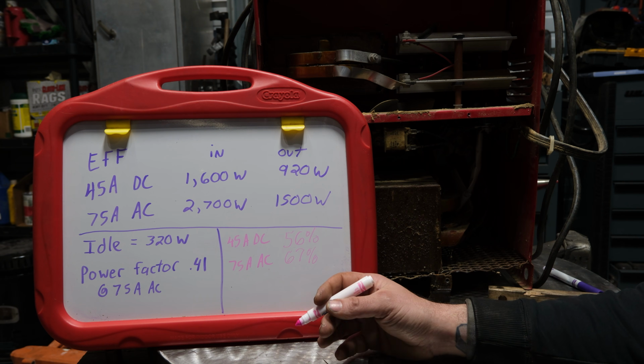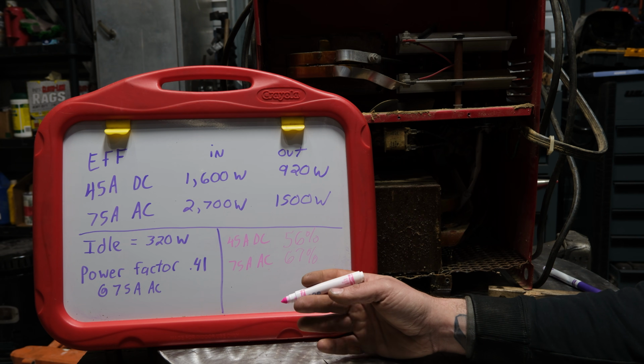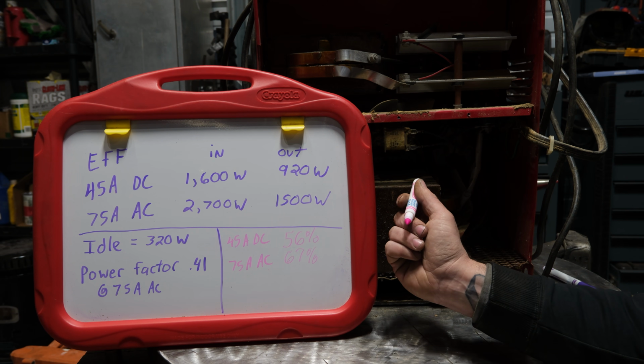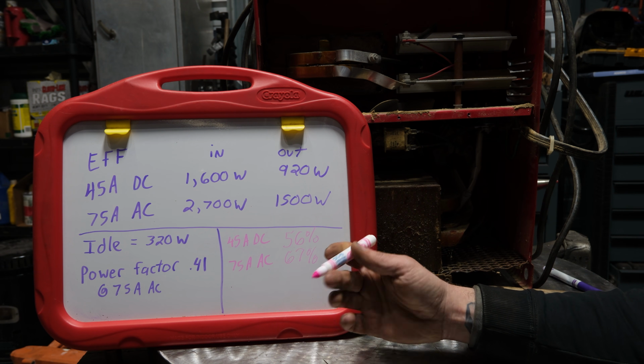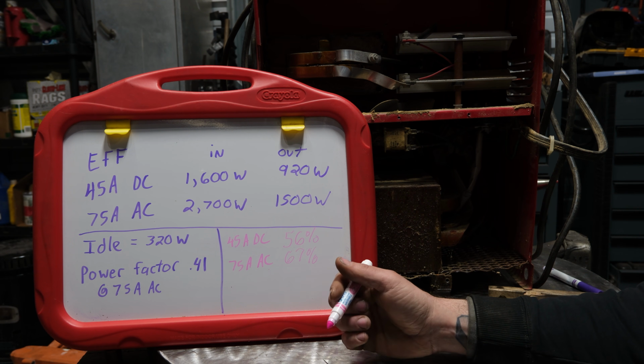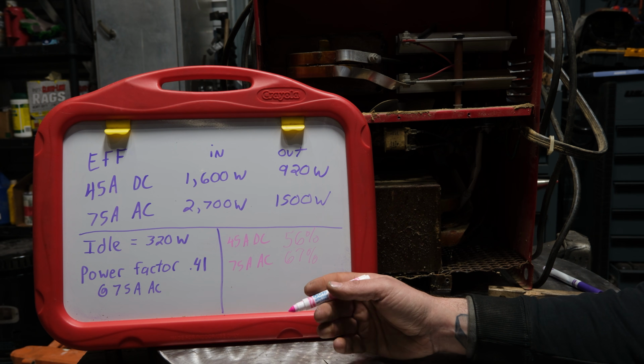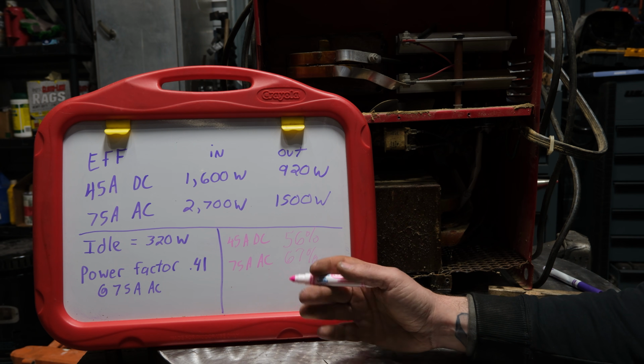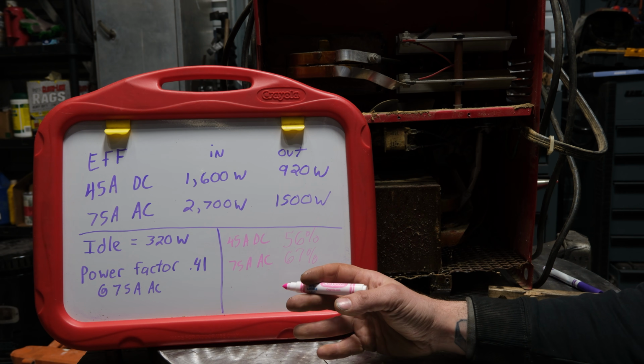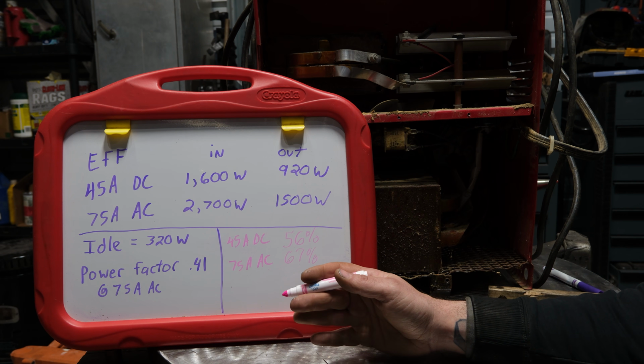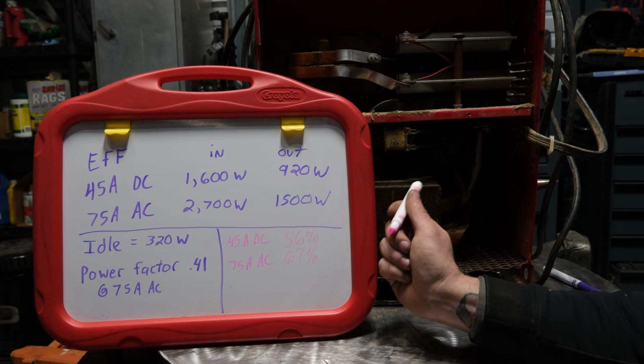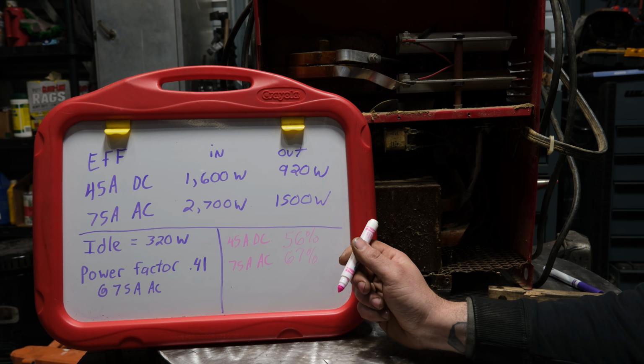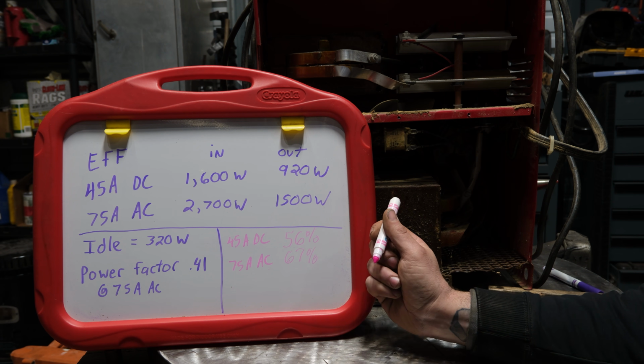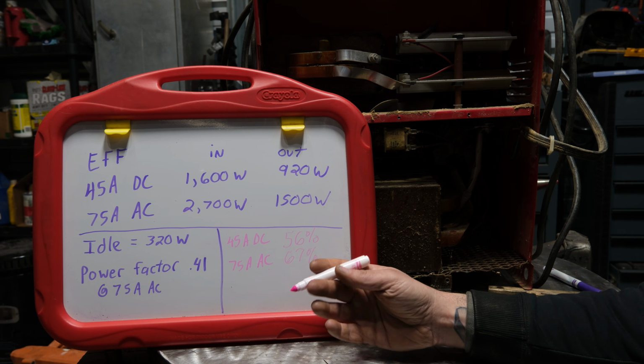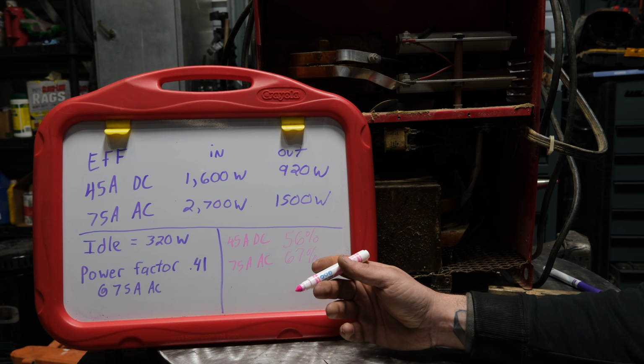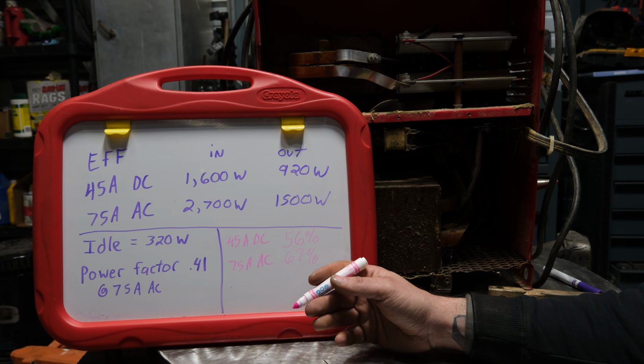That's why when guys ask me what welder should you run on a generator, I tell them don't run one of these on a generator. The poor power factor is going to be an absolute nightmare to deal with. You'll have to deal with tripped breakers and the AC waveform coming out of the generator deteriorating because the power factor, the reactive power, is so bad. Long story short, you should never run one of these on a generator if you care about the generator. This thing doesn't care about the quality of power going into it for the most part, but the generator will get smoked running this on it more than likely.